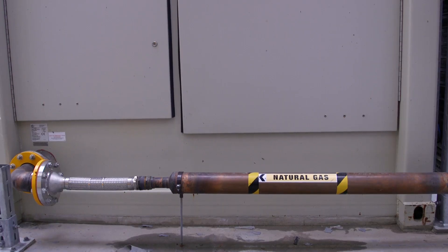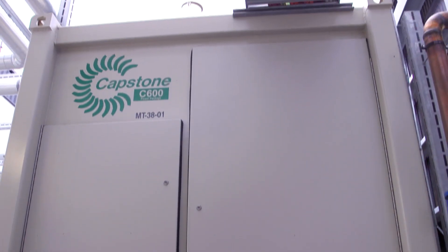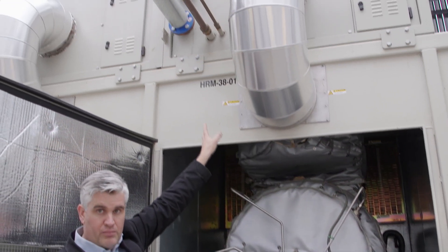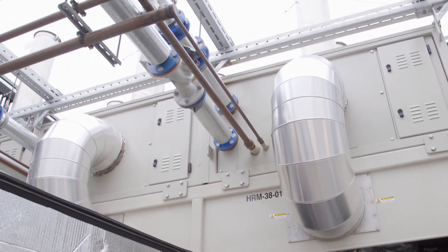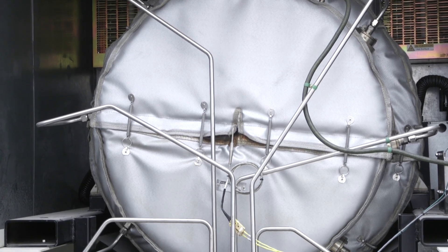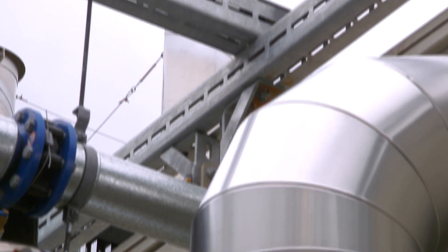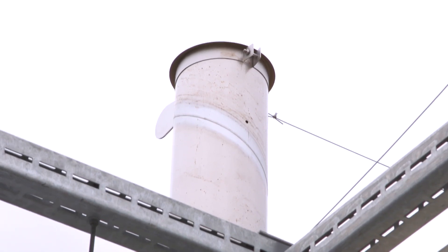The TriGeneration system converts gas into electricity and then we capture that waste heat and use it for heating and cooling across the precinct. The site is the first in the world to use Capstone's new onboard heat recovery units. Each 200 kilowatt unit has its own hot water heat recovery unit which is mounted on the top. The micro turbine is able to control this heat recovery unit, and if the site has times where it needs more power than heat, the micro turbine controls a bypass within the heat recovery system, sending any additional excess heat out of the flue.